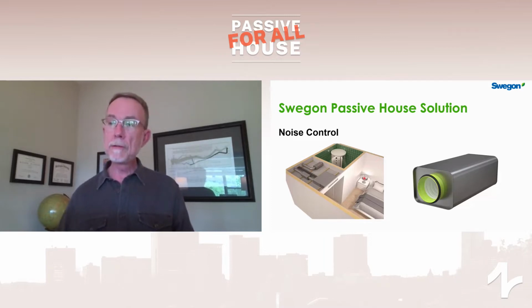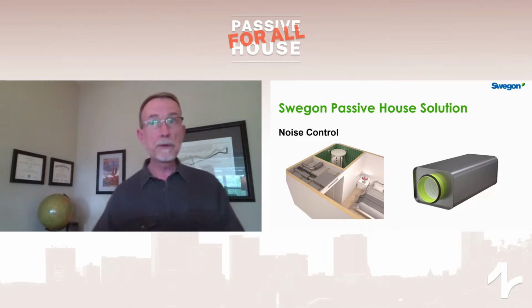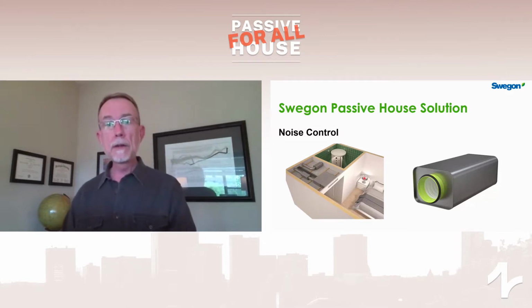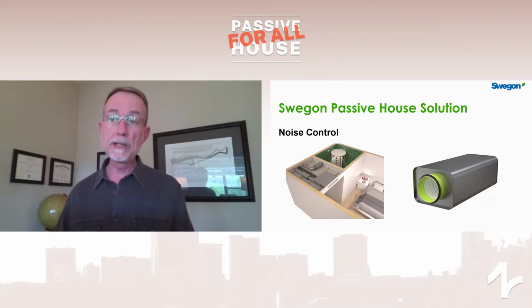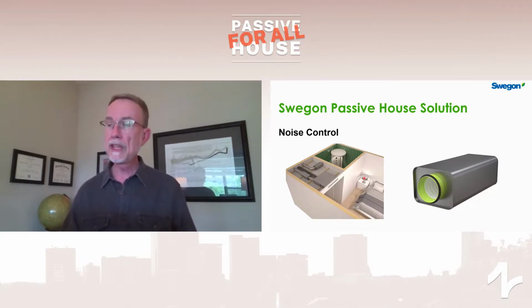And when it comes to sound control, here's an example of how a hotel room might benefit from local sound control. We already took a question about excess noise. In this case, we always put the dampers upstream of the attenuator. So this attenuator, to give you an idea of scale, this is about 2 feet long in its smallest configuration. They also get much larger. But these attenuators are designed specifically for the sort of noise you would get in a building ventilation system, and also designed to prevent crosstalk, important in a hotel, and to silence any system noise that would be residual.